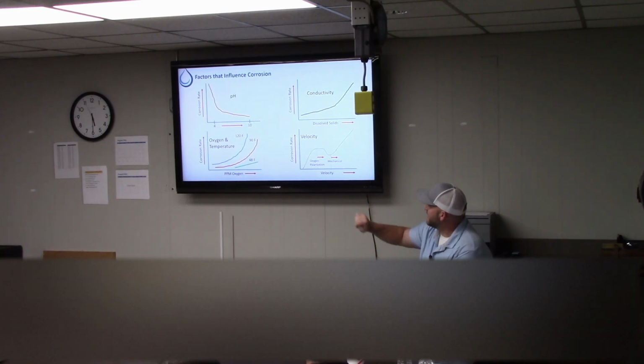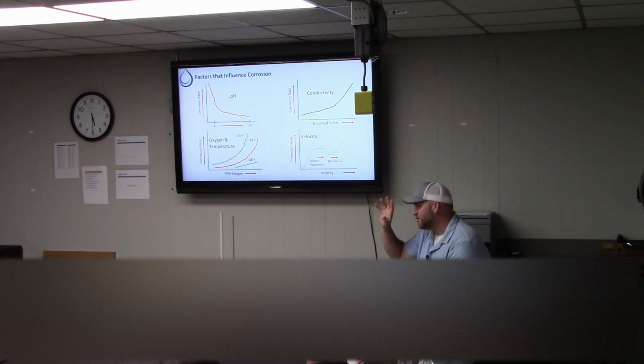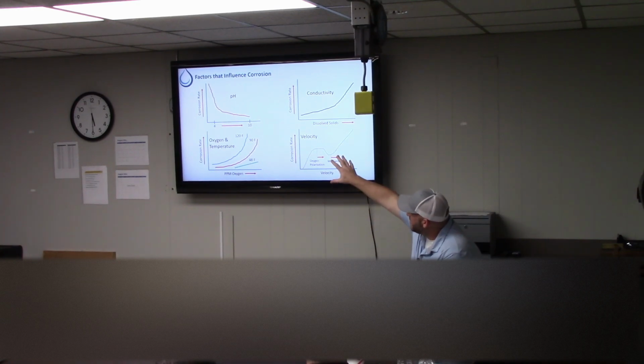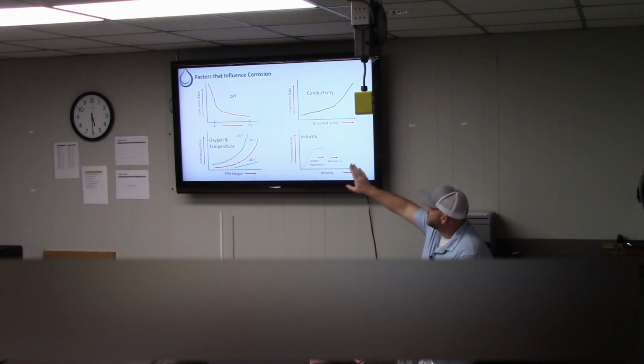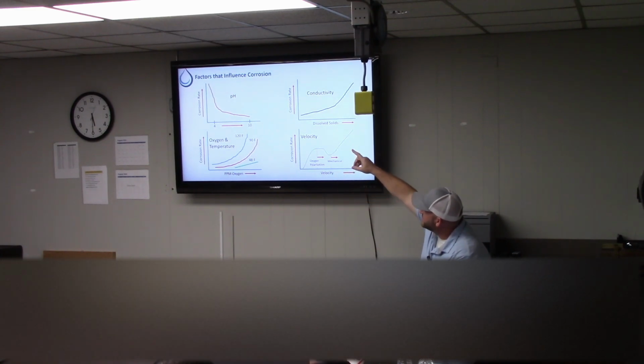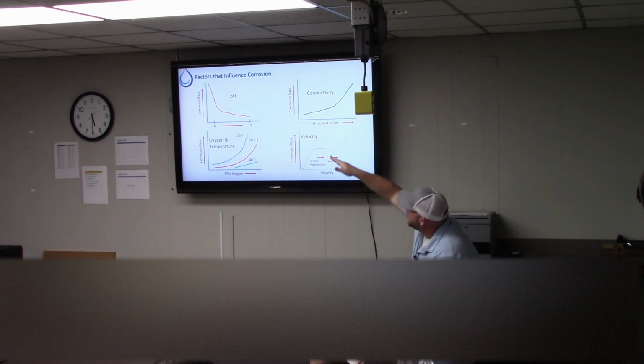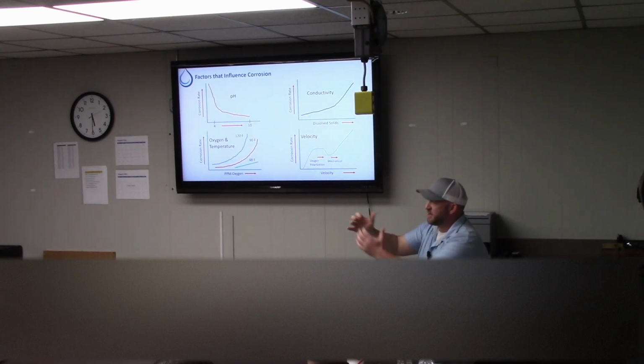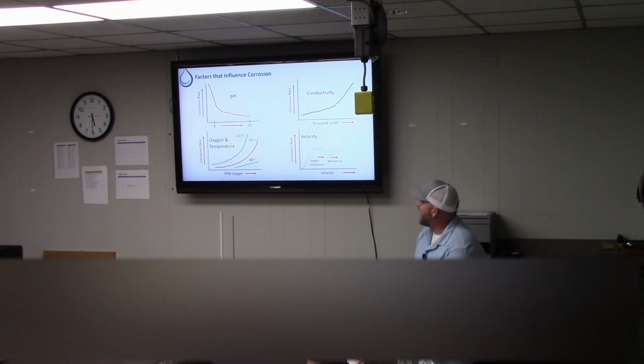The four, maybe five, things I'd like to touch on are pH. You'll see, very basically, that the corrosion rate will increase as the pH is lower. As the pH increases and gets more caustic, more basic in nature, the corrosion rate tends to go down. This is why we don't mind when your cooling tower pH is upwards of 9.